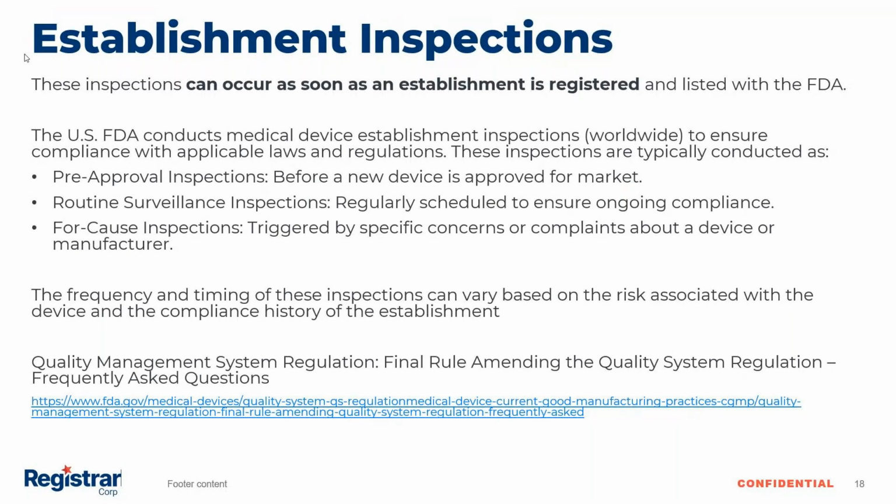And then you have the class 2 devices with a 510(k), and that should be around every 3 to 4 years, depending on the case, but it can change anytime given the course of the inspection. Or you might get lucky that FDA is in the neighborhood and says, hey, let's stop by because we are just around. So there are a lot of things that can trigger an inspection.